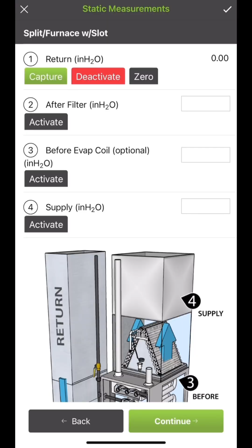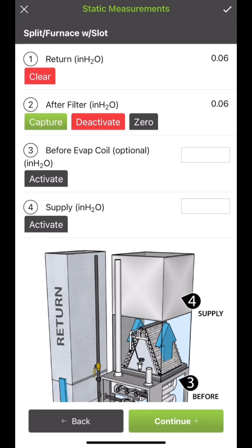Now we're going to activate the probe that we have in return, hit the activate button, and we've got to give it enough time, set it in there. We're going to start getting our readings. You have to get enough time for it to settle down. May take a few seconds. See, we've gone from 0.03 to 04, 05, 06. And keep letting it go. Looks like we've settled there, and we're going to press the capture button.